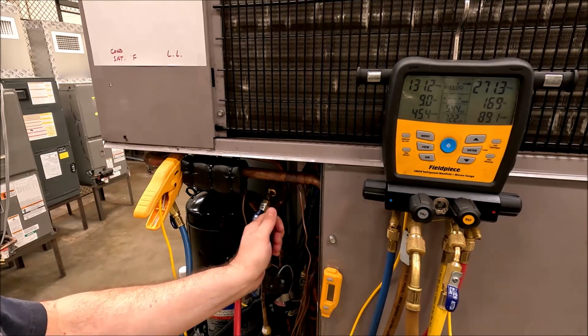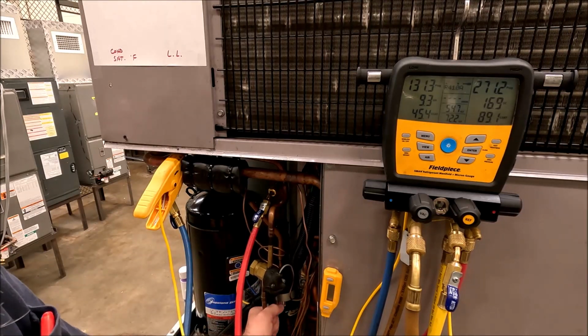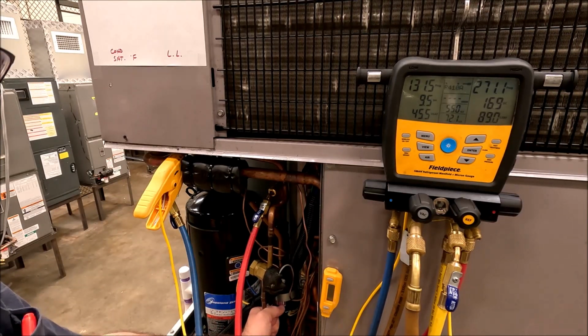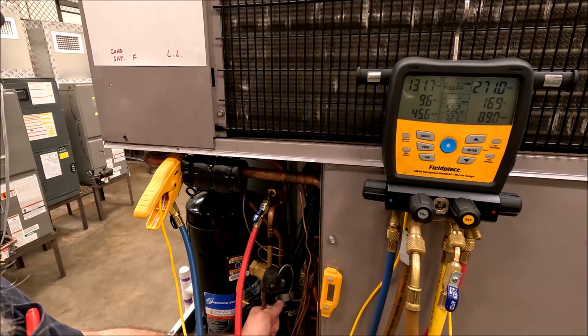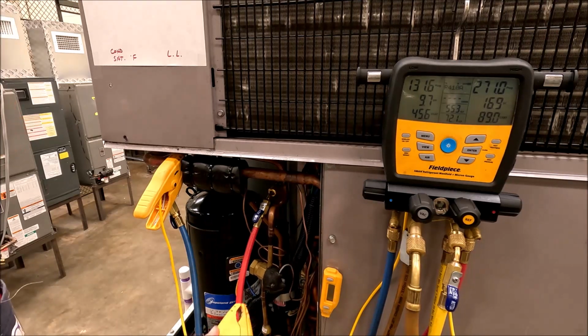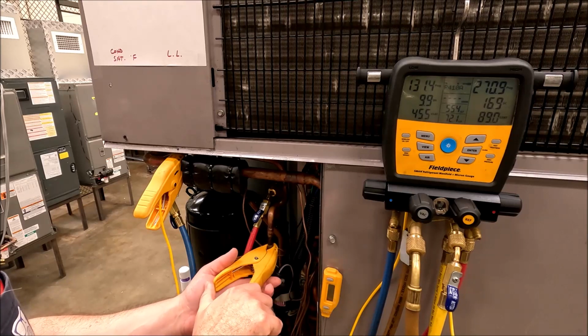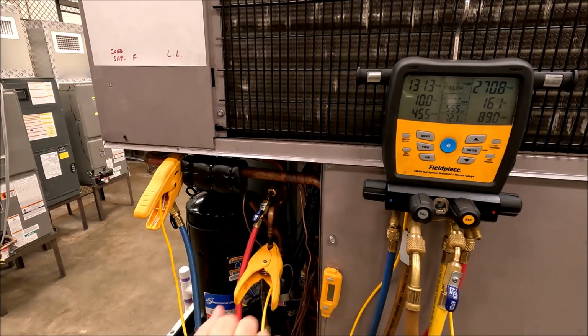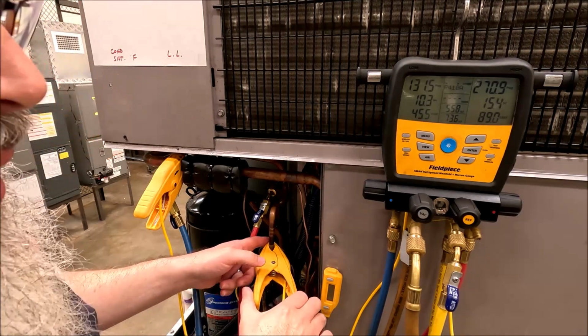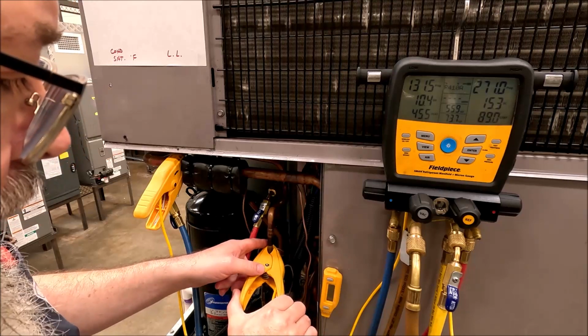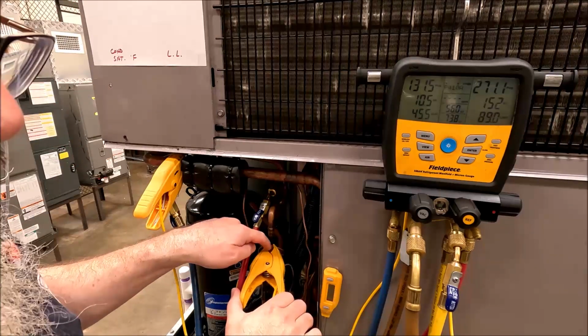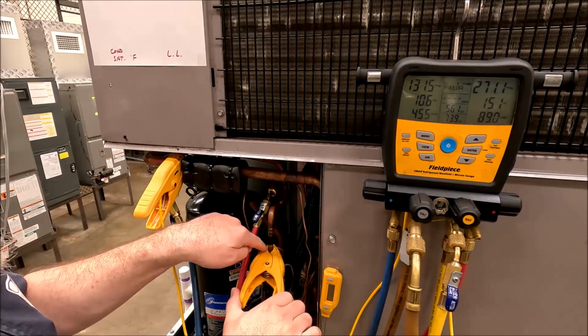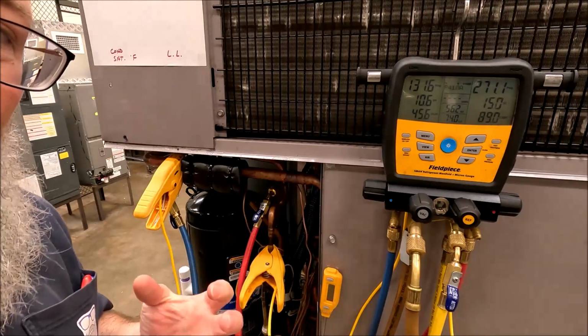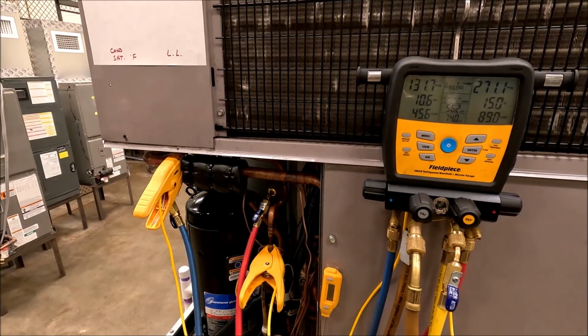You can grab it, it'll be warm here. On the other side, it'll be cold. Even if it don't feel warm, if the other side's cold, then the first side's warm, right? So we're gonna take and we're gonna clamp it right there. And it's a little loose. What you could do is take a piece of insulation. If you felt you weren't getting the proper reading, you could take a little piece of insulation or something and stick under that, and it should kind of tighten it up. So I'm gonna do that, so hold tight real quick.